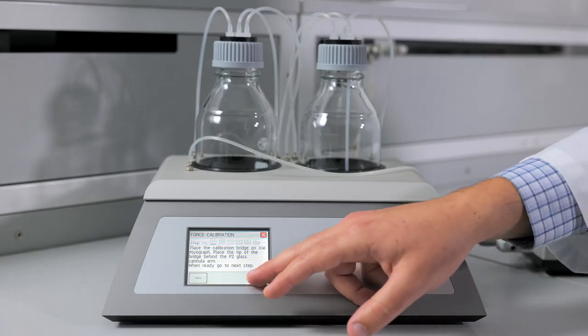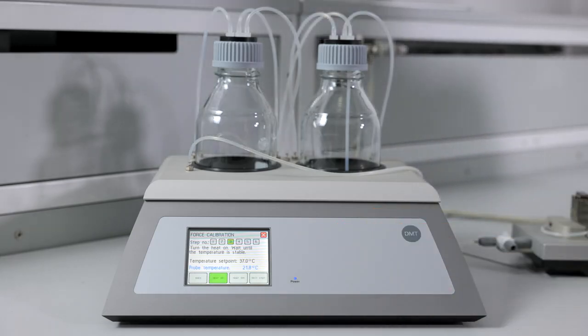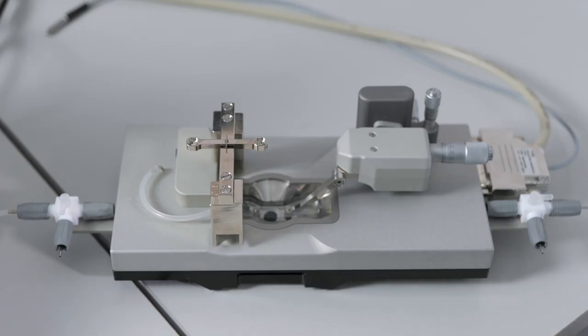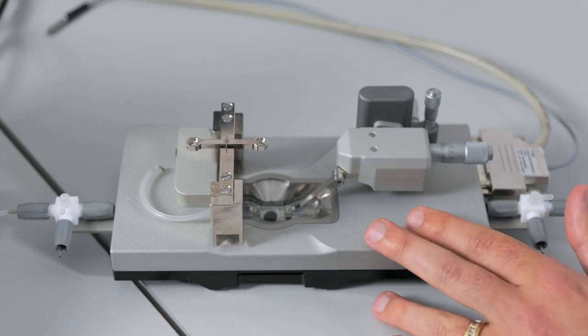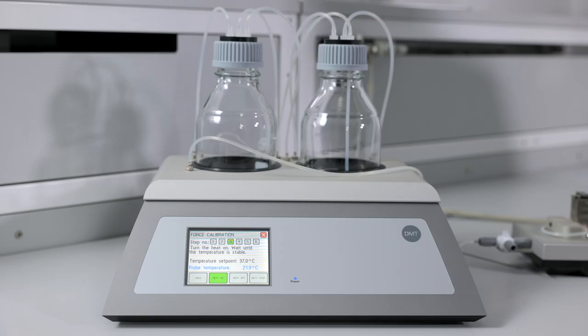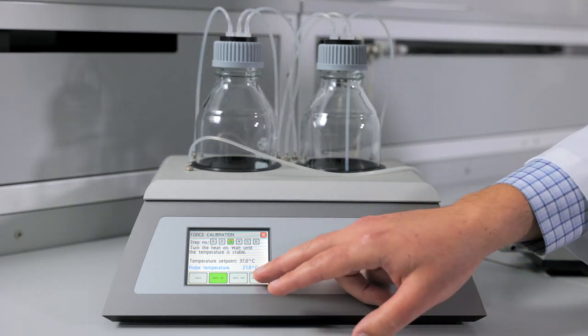Go to next step, which will tell you to make sure that heat is on. The force calibration is best performed under experimental conditions with the heat on and water or buffer in your chamber at the same volume you will use during your experiments. You can also do this at room temperature, but you do not want to do the procedure while the system is warming in the first 20 minutes after turning on heat. We will go to the next step.